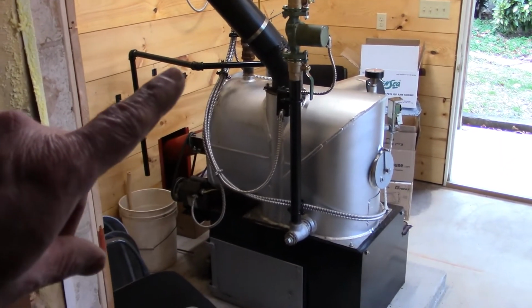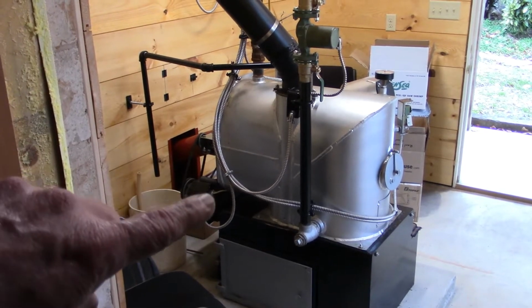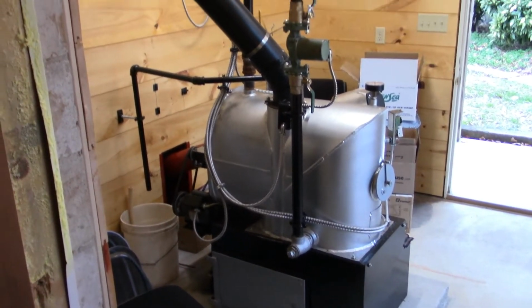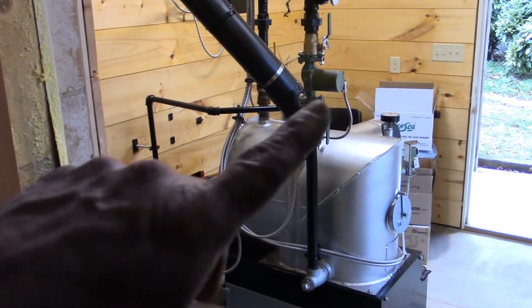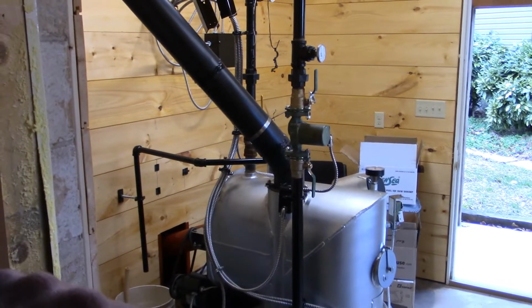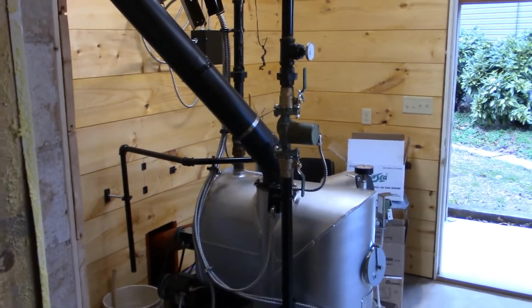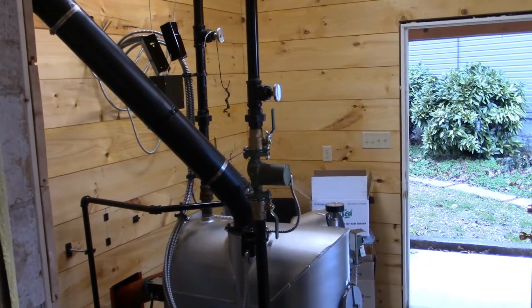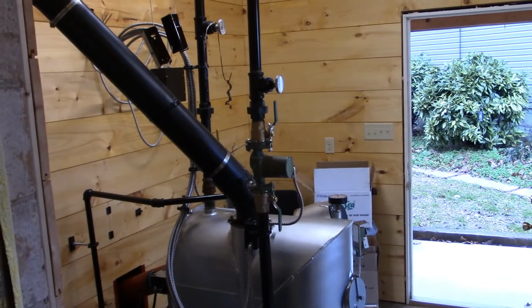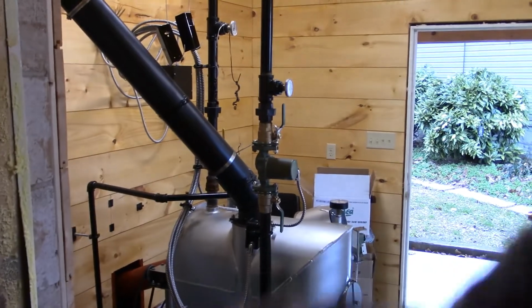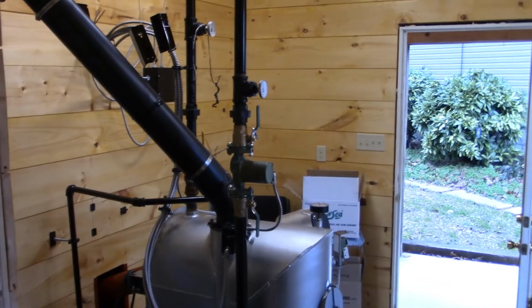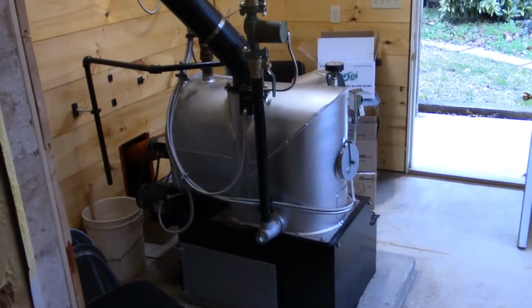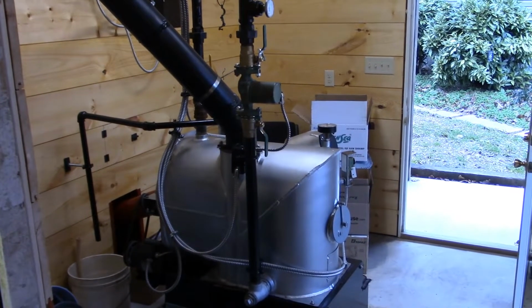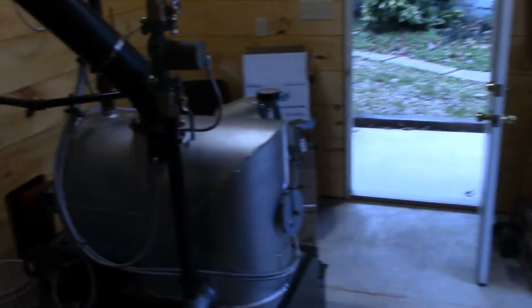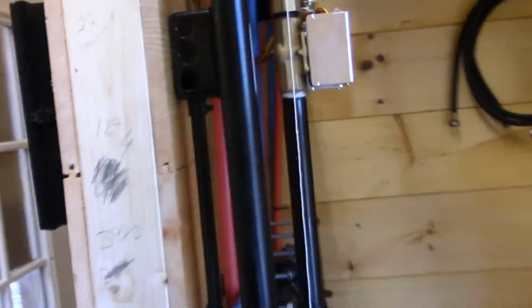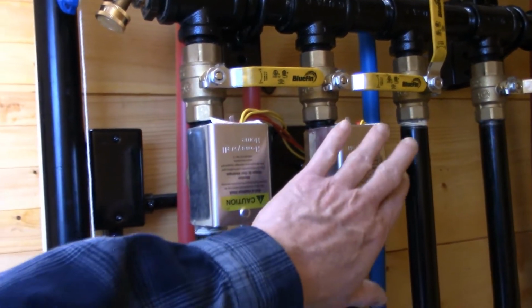We extended the pressure relief valve pipe out so that it was coming down right by the motor, so it was going right on that electrical box before. And we wired the pump, so in this setup the pump runs 24/7 through the headers into the DHW zone, the domestic hot water zone, and into the radiant floor loop, which is controlled in the house. So basically we just constantly pump hot water to that and it regulates itself. The heat exchanger in the basement of the house is hooked up with a zone valve, as well as the one in the basement of this outbuilding. There, you just heard it close. That was this zone valve closing.